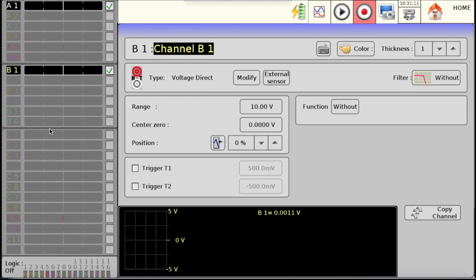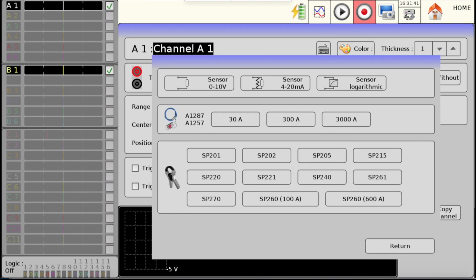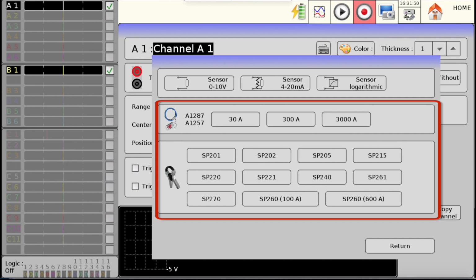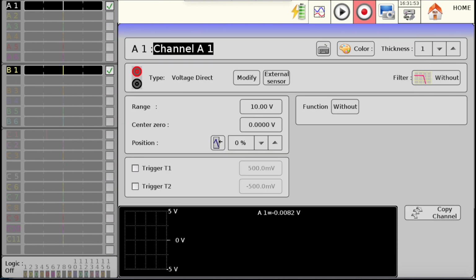Let's take the example of the recording of a sensor, such as a pressure sensor in bar. Let's select the channel we want to configure, A1 for example. Then, let's define the type of physical value we want to record. Here, a direct voltage for a 0-10 volt sensor or a 4-20 mA sensor. The channel can be automatically configured by pressing External Sensor and selecting 0-10 volt sensor, 4-20 mA sensor, current clamp, etc. In our case, we will do a manual configuration.